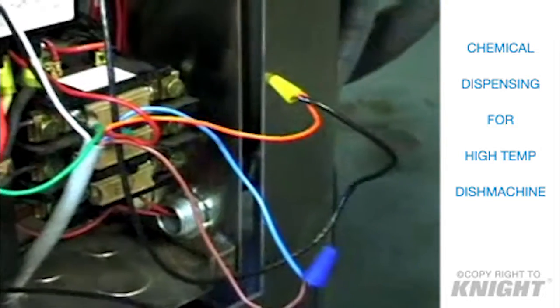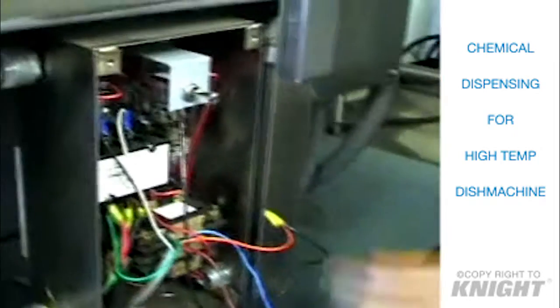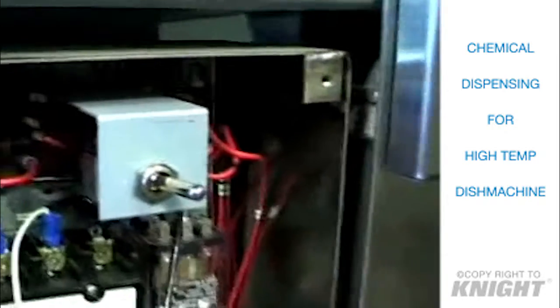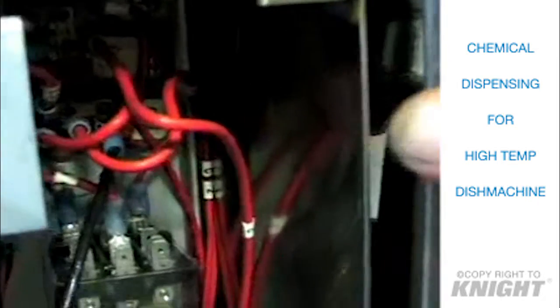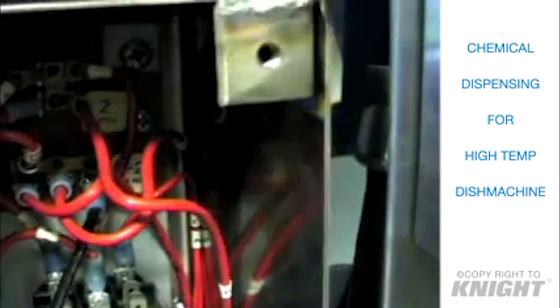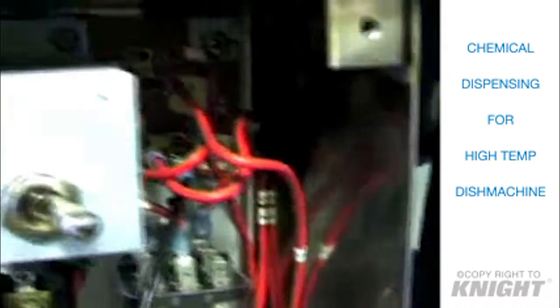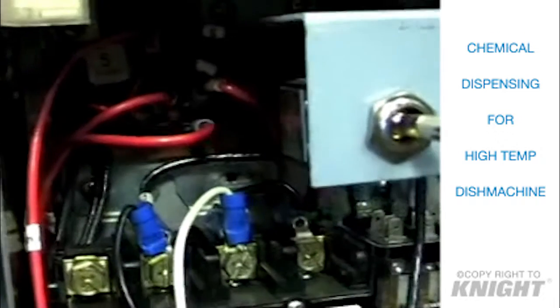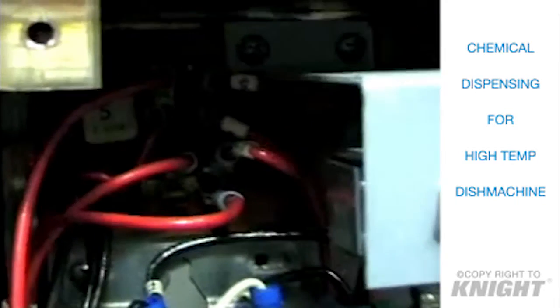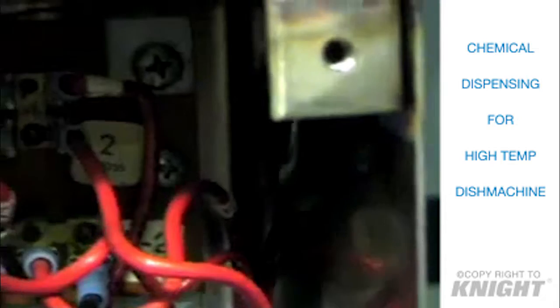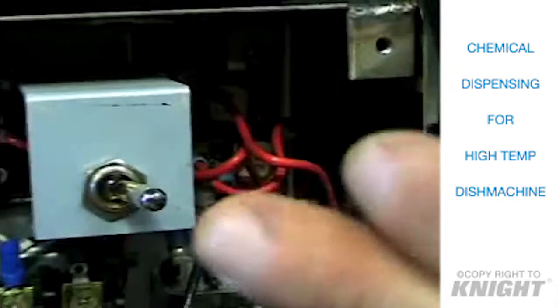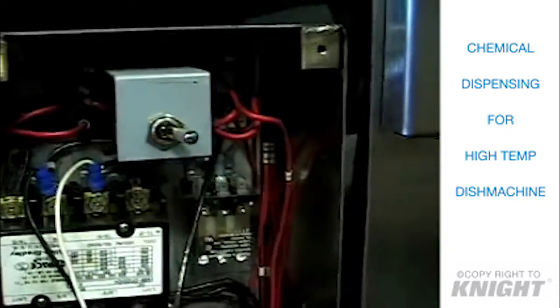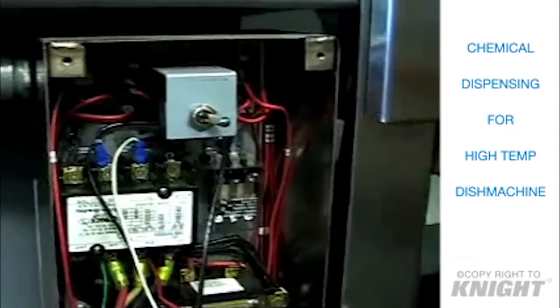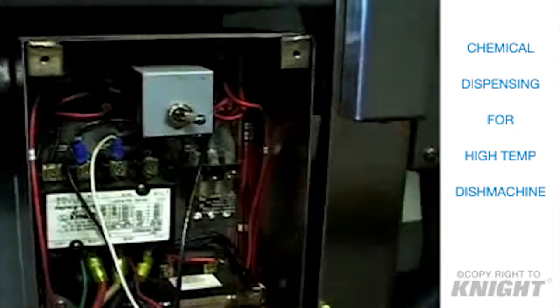If I go into this box, at the top you can see that there are terminals marked at the back. Mark number 2, and on the other side, number 5. All those connections are dead when the machine is in the off position, so the rinse won't work or anything that's connected. All those wires that are connected right now, there's no power to those until I turn the switch into the on position. So when I do that, what that does is it activates those terminals.